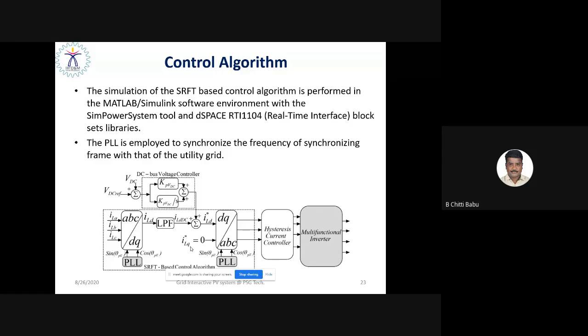So as you are assuming that the grid is in balanced, sinusoidal condition, it implies there is no support of reactive power, because it is balanced, there is no existence of reactive power. Its voltage profile remains constant. So during steady state, you assume that the Q-axis load current component is 0. It implies the grid is connected with a balanced three-phase load. So it implies you need only active current component control.